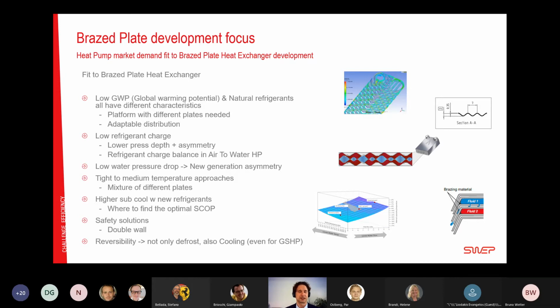There is a push, since most of the refrigerants are flammable, mildly flammable, or highly flammable like propane, to have a low refrigerant charge. So we are working with our pressing depth and the asymmetry and the pitch on our heat exchangers to minimize this refrigerant charge. And we have recently developed a new next generation of asymmetry.